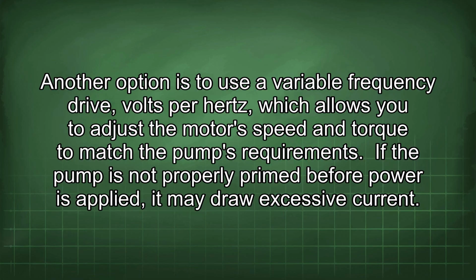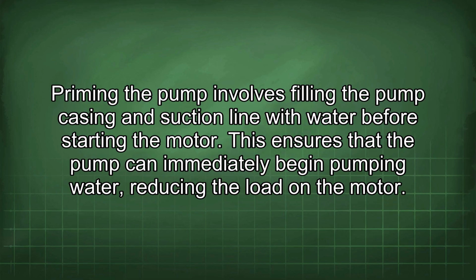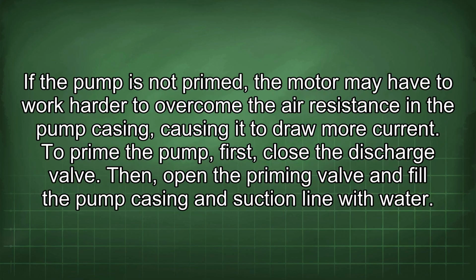If the pump is not properly primed before power is applied, it may draw excessive current. Priming the pump involves filling the pump casing and suction line with water before starting the motor. This ensures that the pump can immediately begin pumping water, reducing the load on the motor. If the pump is not primed, the motor may have to work harder to overcome the air resistance in the pump casing, causing it to draw more current.